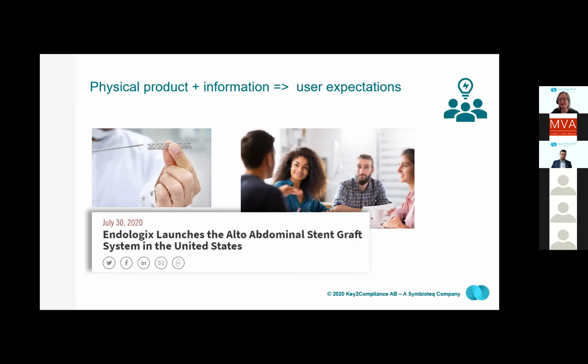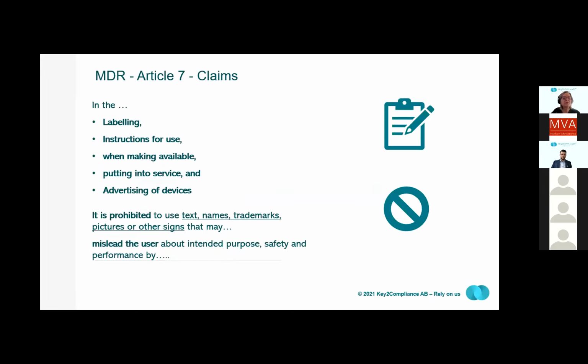So let's take a look at some of the text in Article 7. What it says here about claims is that in the labeling, so labeling is the information placed directly on the device or the package of the device, in the labeling, instructions for use, when making available, putting into service, or in advertising of devices, it is prohibited to use text, names, trademarks, pictures, or other signs that may mislead the user about the intended purpose, safety, and performance.